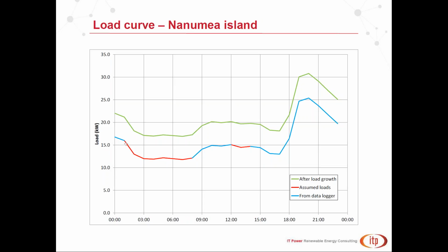The average usage is about 550 kilowatt hours a day. We've allowed for load growth - once people have reliable electricity, they typically add things like fridges and freezers, which weren't viable previously because they'd continuously go through a freeze-defrost cycle without consistent electricity. There's also a significant jump in electricity use during particular times of the year, as people based off the islands come home for special events such as Christmas.